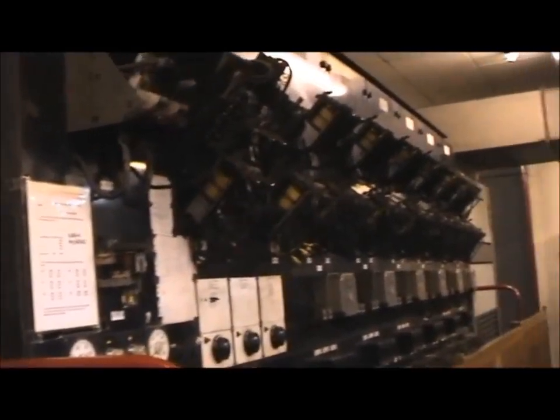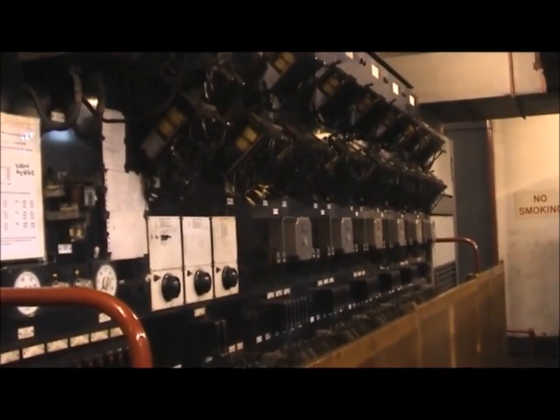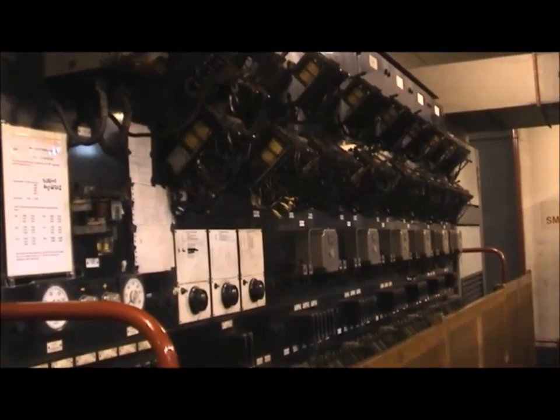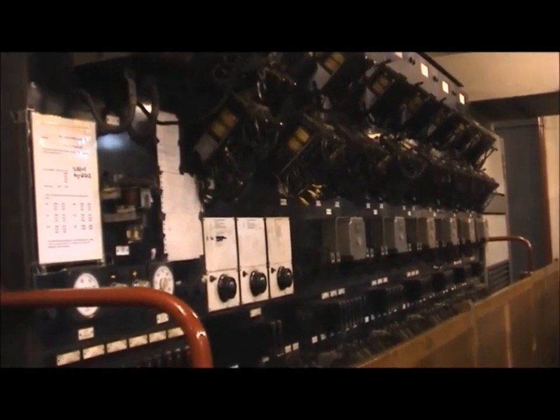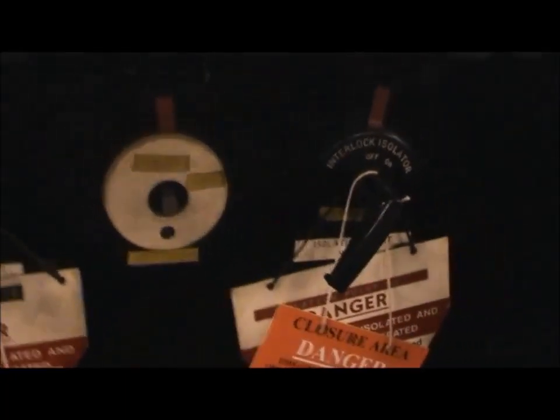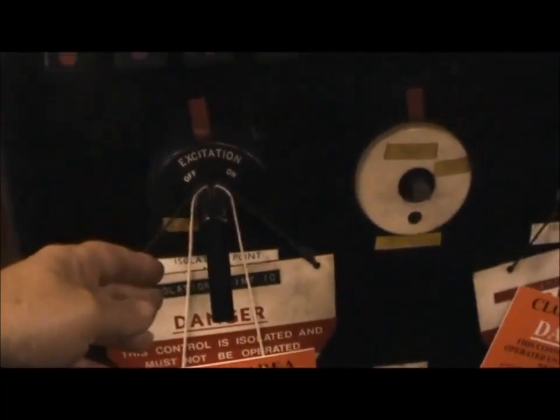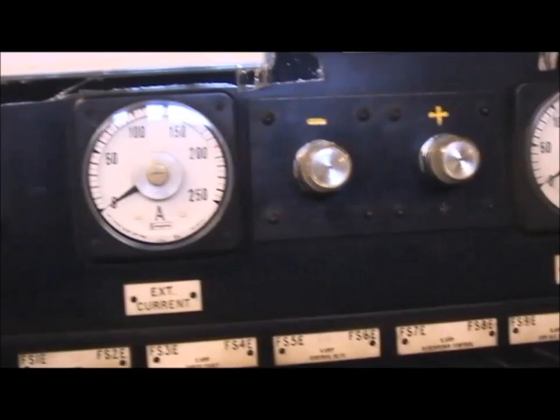This is the stands, the main brake control, sequencing for those. Close the offload isolator. Close the interlock isolator, which then enables us to bring in number 10 switch, and the DC excitation will appear.